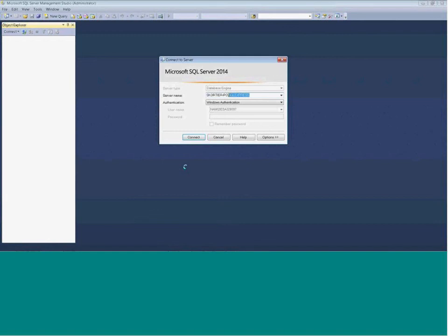But to point it to this database, it's SQL Express. When I configure this in InduSoft Web Studio, I'm not going to use my PC name, because if I deploy this on another computer, I don't want it to look at the database on my computer. I want it to look at the database on the computer that it's running on. Also notice that I'm using Windows Security.